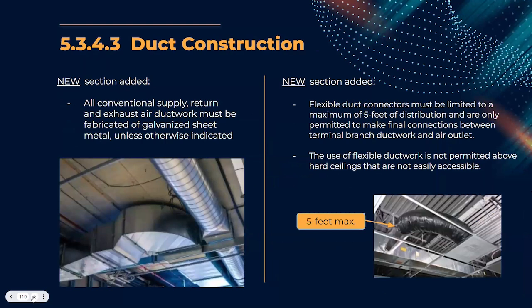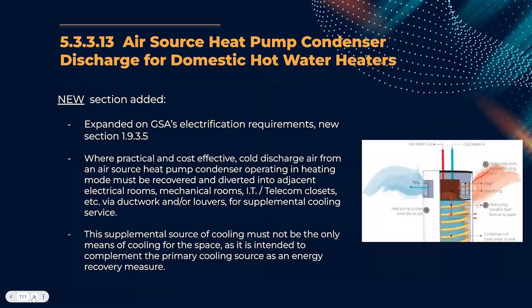This I don't think was previously immediately obvious, but all ductwork for all conventional system types must be galvanized sheet metal unless otherwise indicated. And regarding the use of flex ductwork, there's a 5-foot maximum limit for flexible ductwork. And a reminder that flex ducts are not permitted above hard ceilings, only accessible ceilings. Next slide, please. Where practical and cost effective, cool air rejected from an air source heat pump that is in heating mode is to be recovered and delivered to adjacent spaces requiring cooling, such as electric or IT closets. That's a brand new requirement for this year.